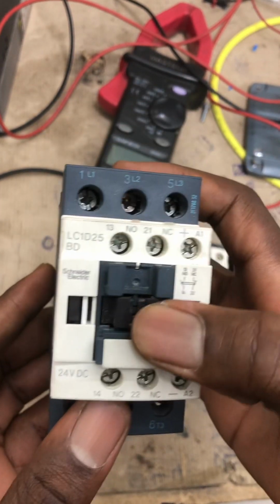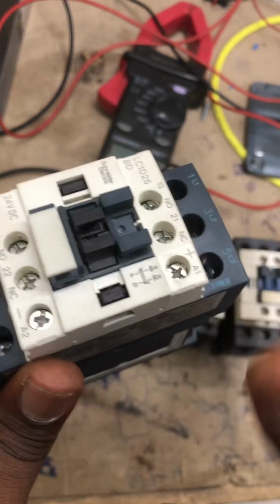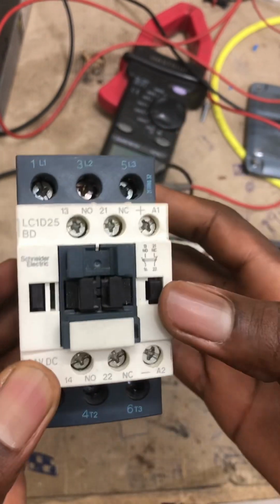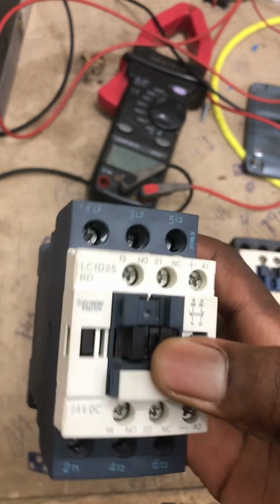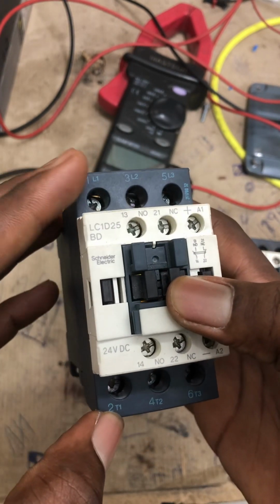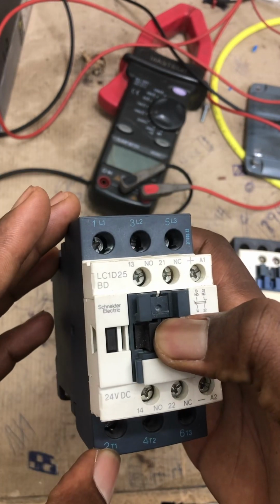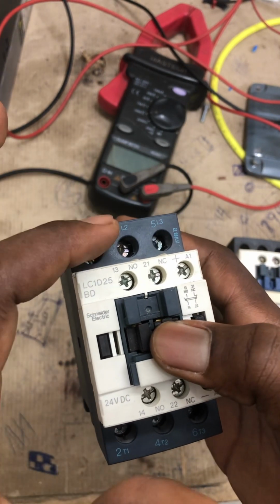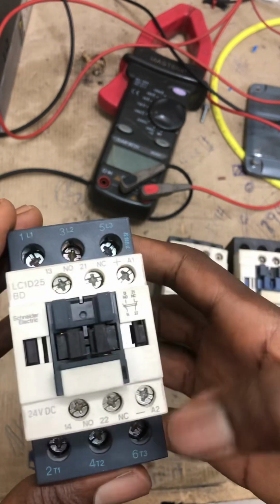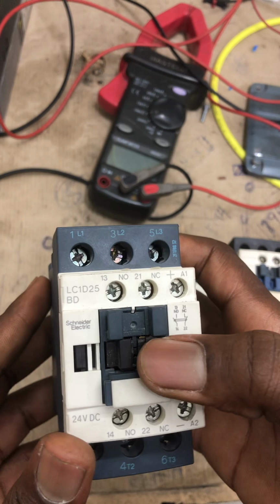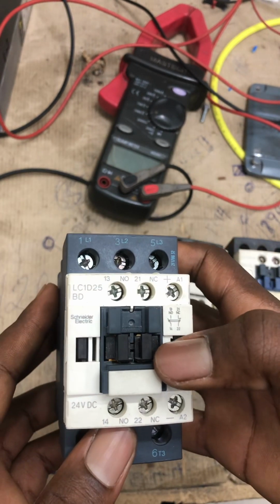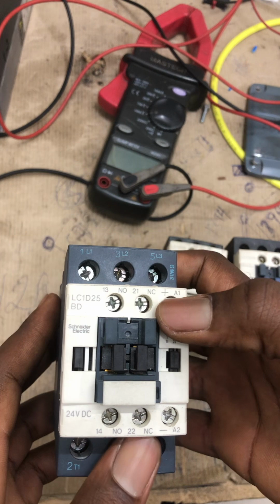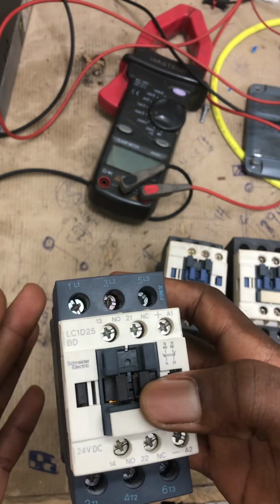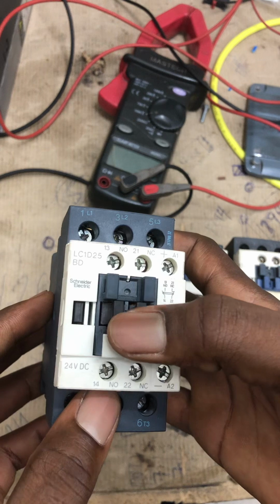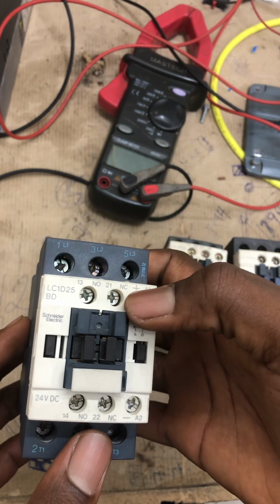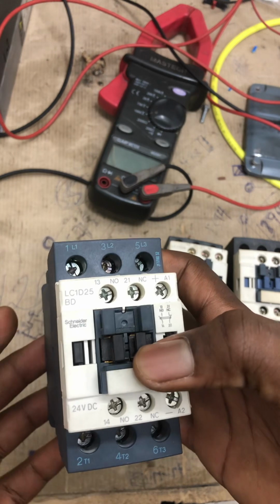The contactor operates in such a manner that when the coil of the contactor gets energized, the contacts change states. As it stands now, 1 and 2 are normally open, 3 and 4 are normally open, 5 and 6 are normally open. And then the auxiliary contacts: 13, 14 are normally open, and 21, 22 are normally closed. So when the coil gets energized, 13, 14 becomes closed, and 21, 22 becomes open.